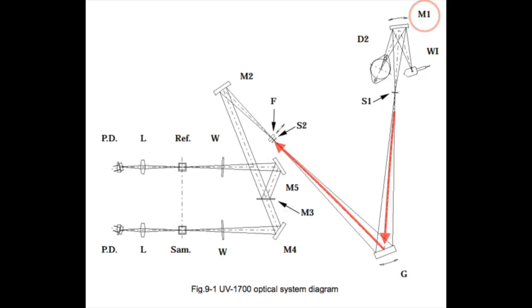The light then enters the monochromator through the entrance slit, is reflected off the diffraction grating and leaves through the exit slit.